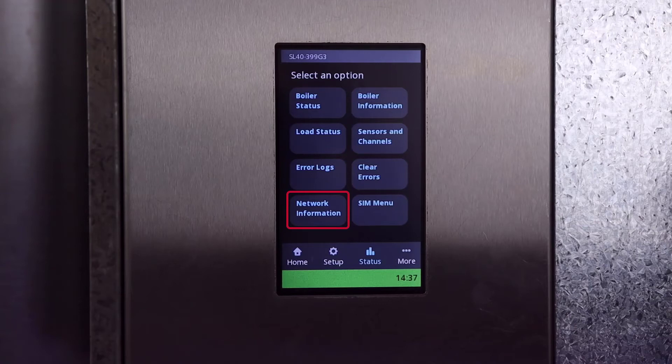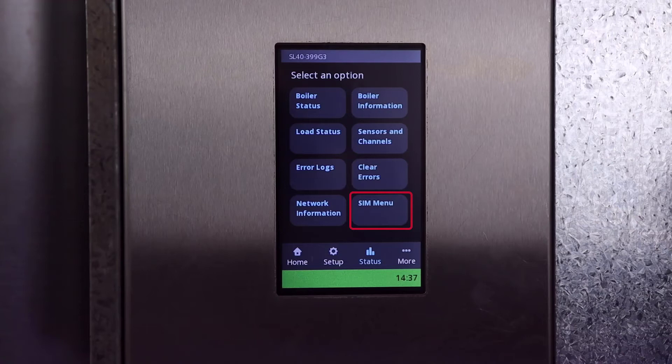Network information is where you can find details such as your current IP address, portal status, and MAC address. SIM stands for Safety Ignition Module. This tab is used for diagnosing the SIM, as well as demonstrating for an inspector the operation of the low water cutoff and water high limit safety circuits. You won't find this sub-menu on older models that weren't built with a SIM.